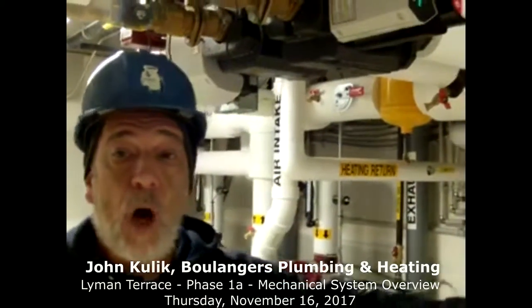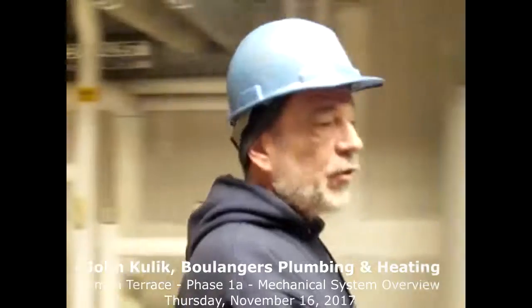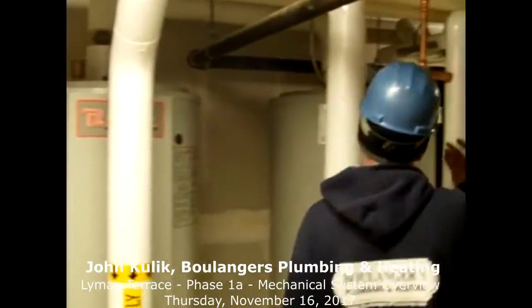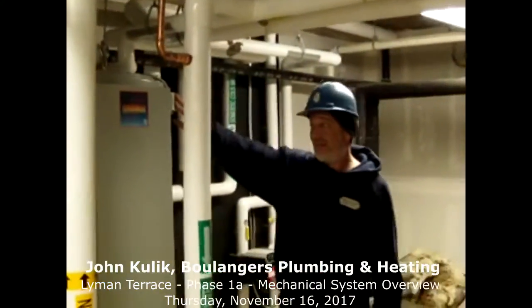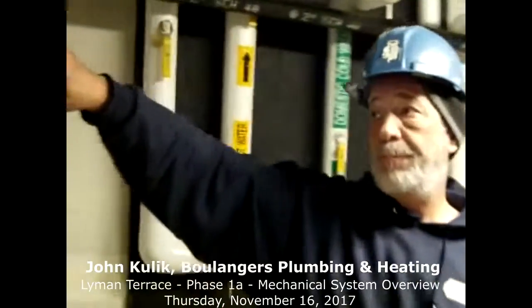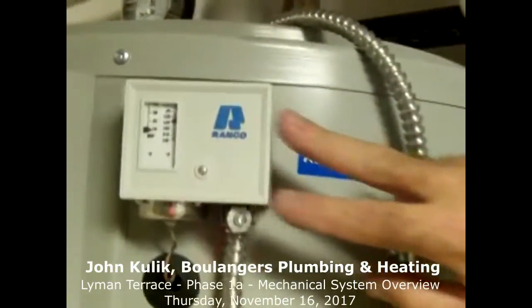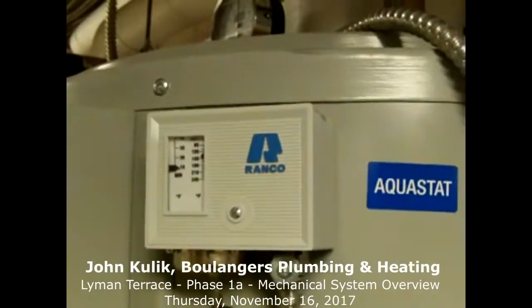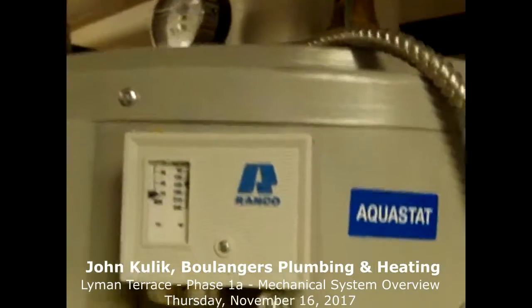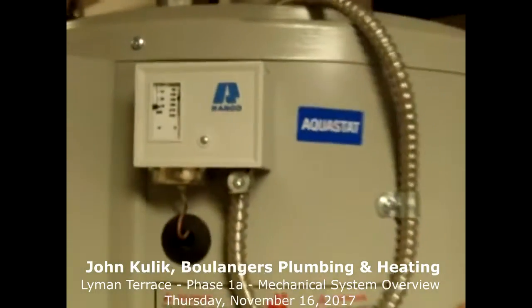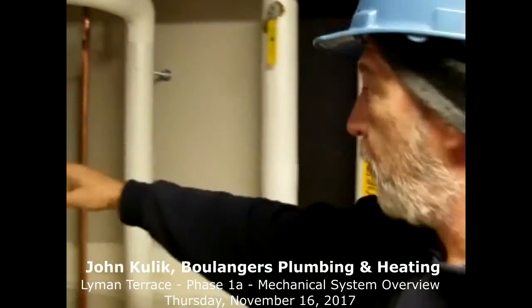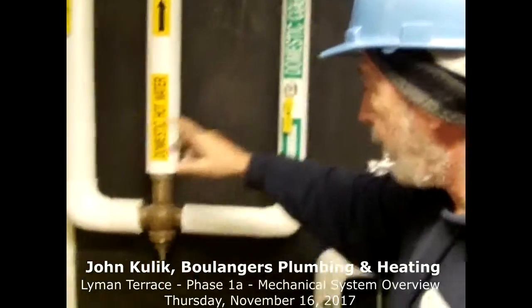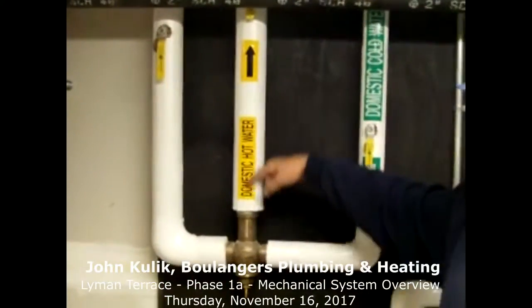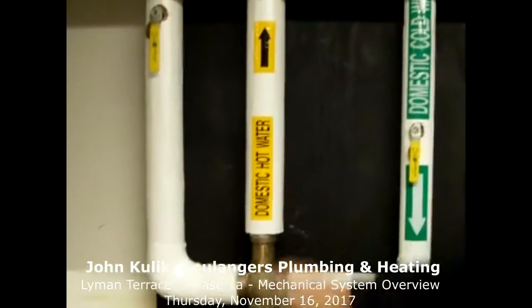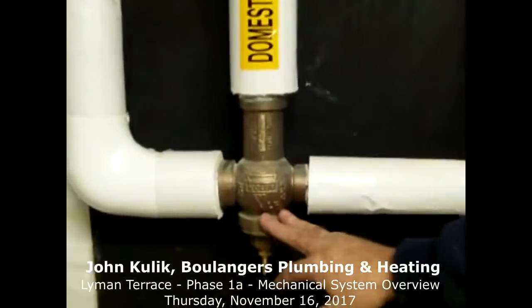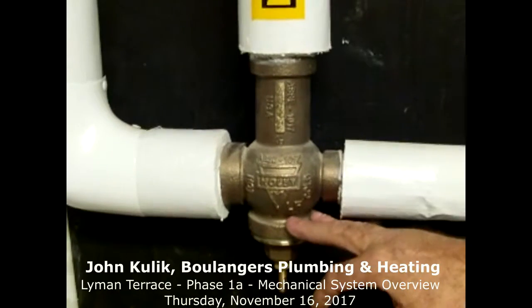When there's a call for hot water, people are drawing, the tank gets cooled down in temperature. We have the temperature setting on the tank here with this thermostat. Okay, the temperature of the tank is elevated. It's higher than what's going to be coming out of the faucet. Why? Capacity control. We want to have more stored water than we need so that we can take that higher temperature water and mix it with cold water to give you a blend or a mixed temperature through the hot water mixing valve. And this is for the domestic water at the tubs, showers, and sinks.